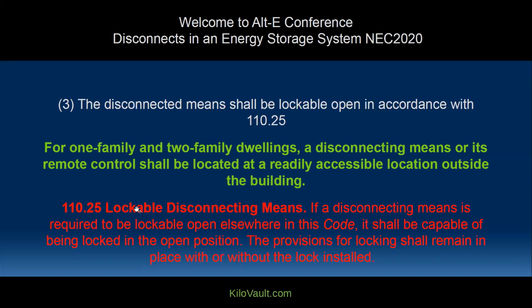So, a little definition for the lockable disconnect means: if the disconnect means is required to be lockable in the open position elsewhere in this code, it shall be capable of being locked in the open position. This provision for locking shall remain in place with or without the lock installed. So once you switch it to an open connection, it shouldn't need a locking device to keep it there by itself. It should stay there. It shouldn't be auto-resetting of any form or anything like that.